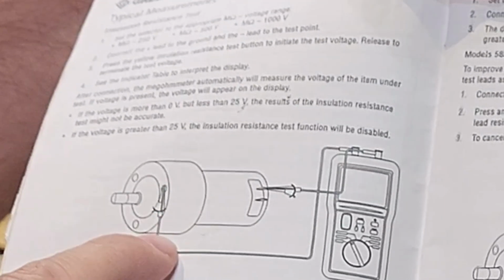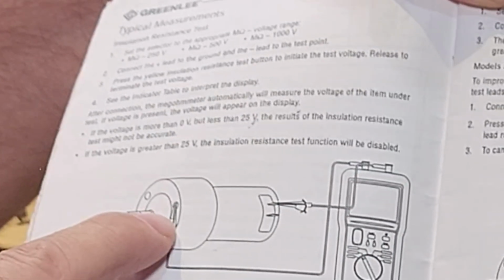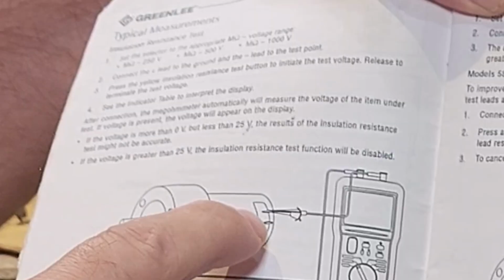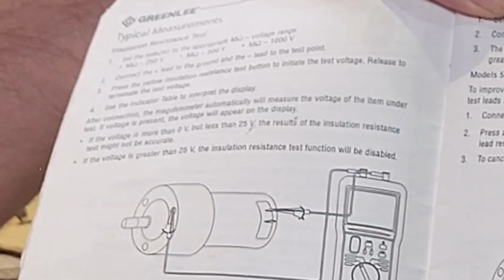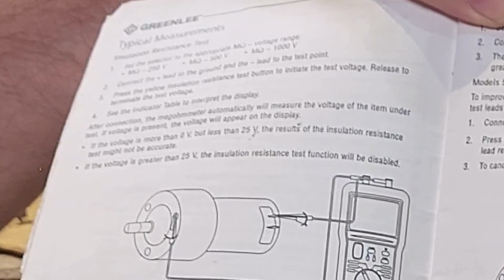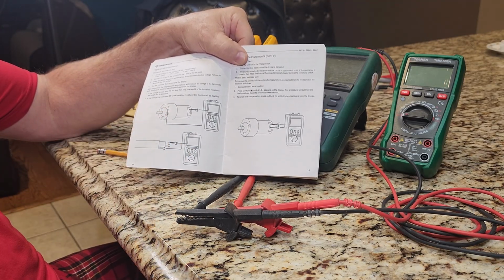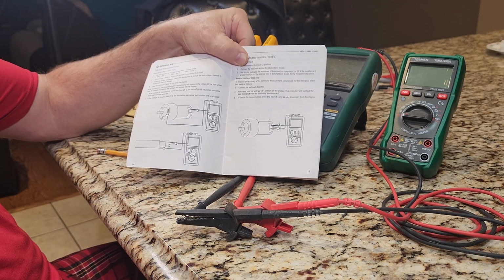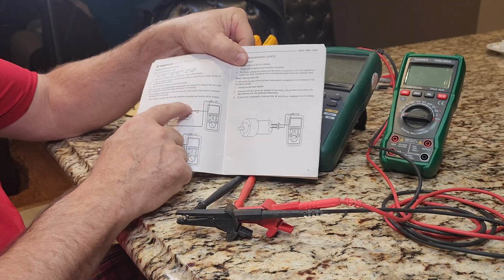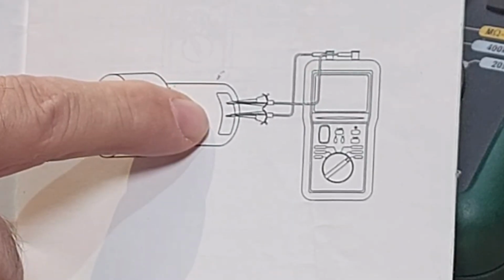And here's a clear example of the positive wire actually on the case of the motor, and then it's measuring one of the windings. So under this application, you should always read open loop. There should never be a continuity or any type of resistance from a motor winding to the metal of the case. If there is, you know you have a major problem. And if it's completely open, well, that's good.